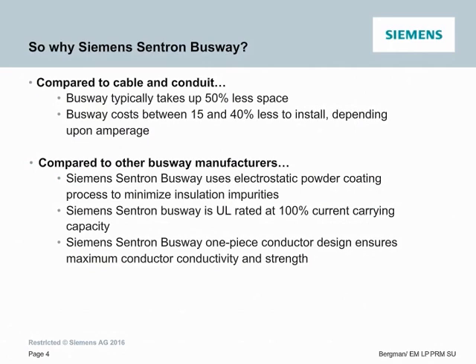Okay, just to recap real quick, why the Siemens SENTRON busway system? Well, again, compared to cable and conduit, busway typically takes up 50% less space, and busway costs between 15 to 40% less to install, depending upon your amperage. Now, when we compare it to other busway manufacturers, there are a couple pieces that we really need to drive home here. The electrostatic powder coating minimizes insulation impurities to ensure longevity and robustness of the product throughout your facility's lifespan. Also, it is 100% UL rated, whereas other manufacturers are only 80% rated. And the one-piece conductor design means there are no welds in your conductor. This means higher short circuit strength and more effective conductivity.